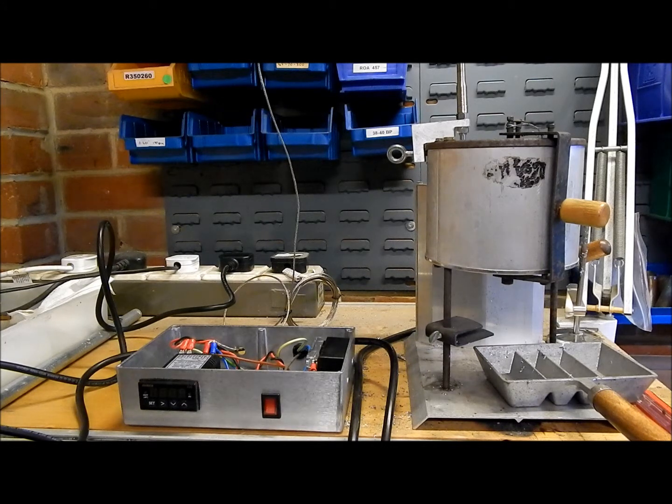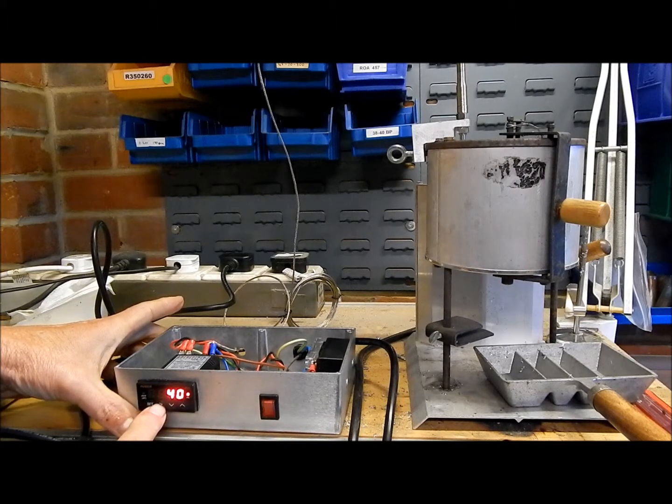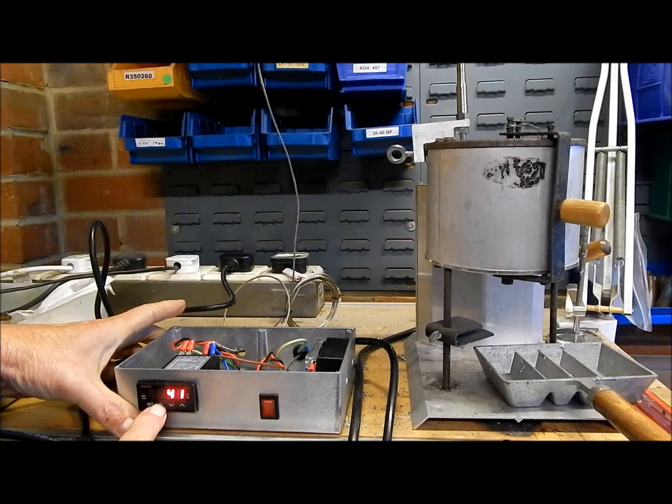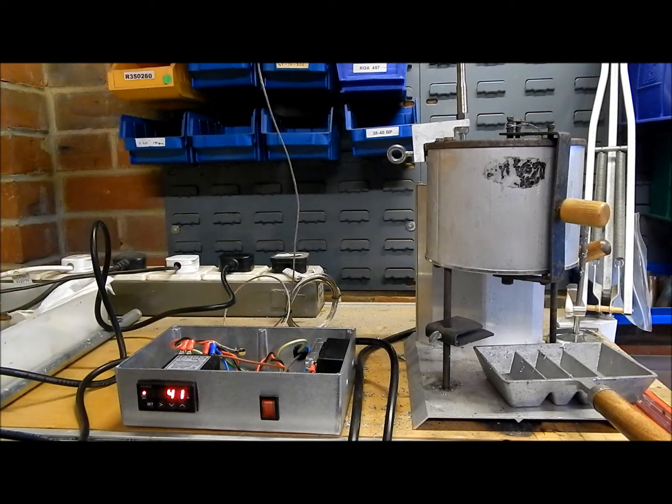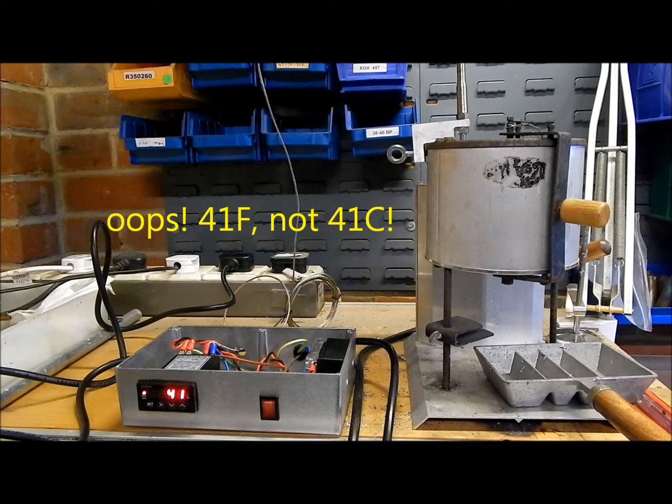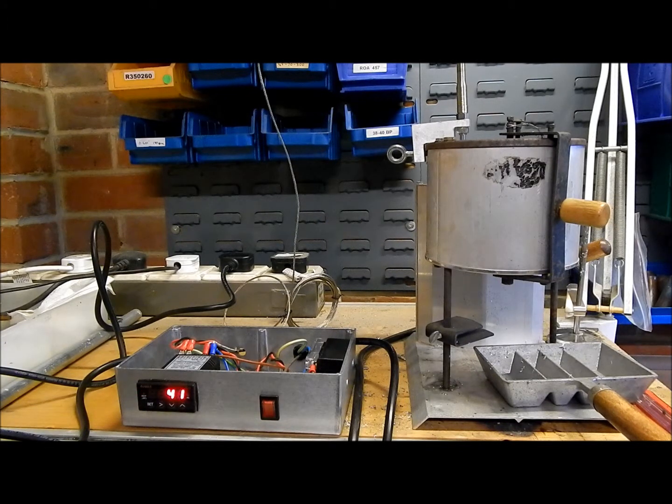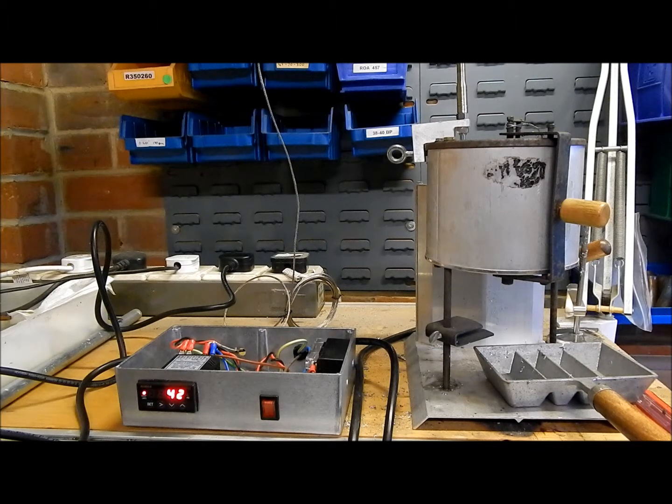I'm going to switch it on and set it up for auto tuning. So at the moment it's displaying the current temperature. A bit cold in here this morning. 41 degrees C. This flashing light here means that it's on the auto tuning cycle. And what it will do, it will heat up to the set point, overshoot and then cool down again. And it will do that at least three times. And when it's done that it can work out the best control strategy for this particular application. So really the user doesn't have to do anything except press a few buttons.